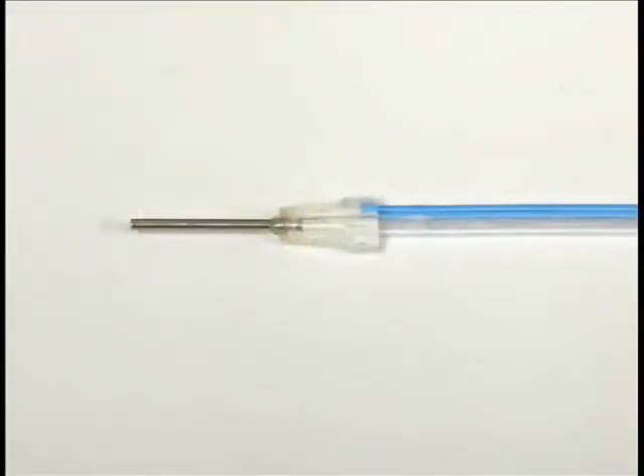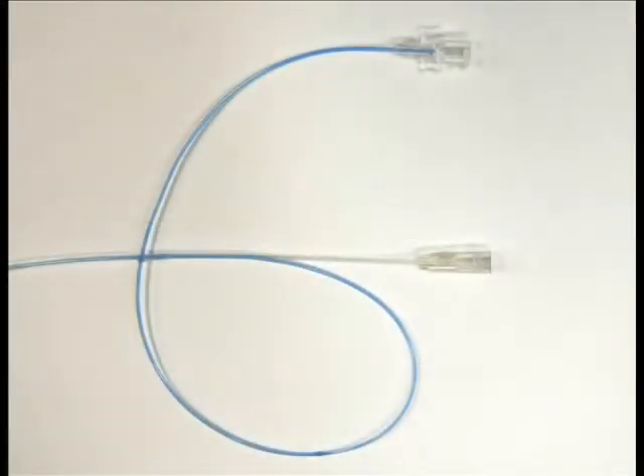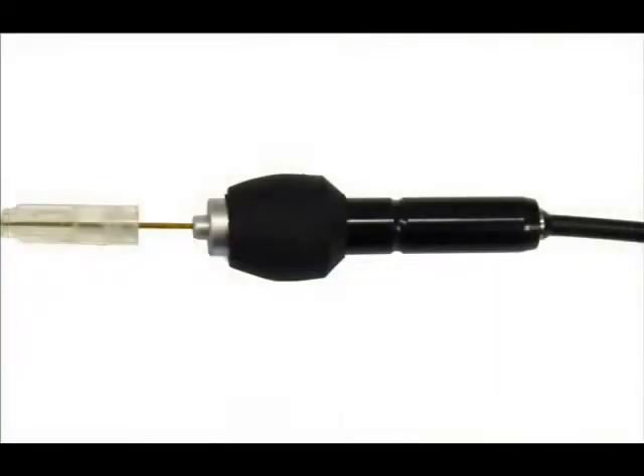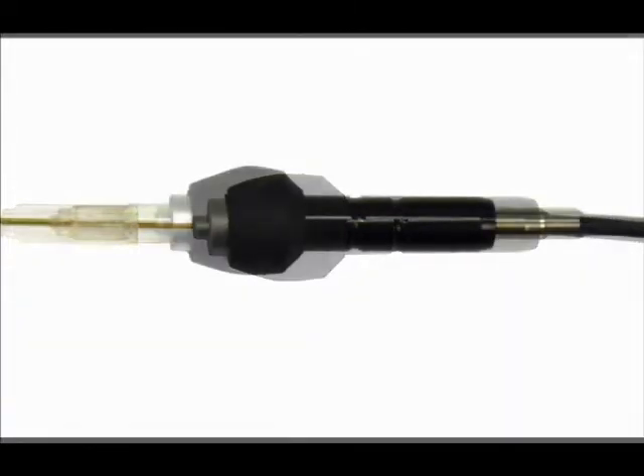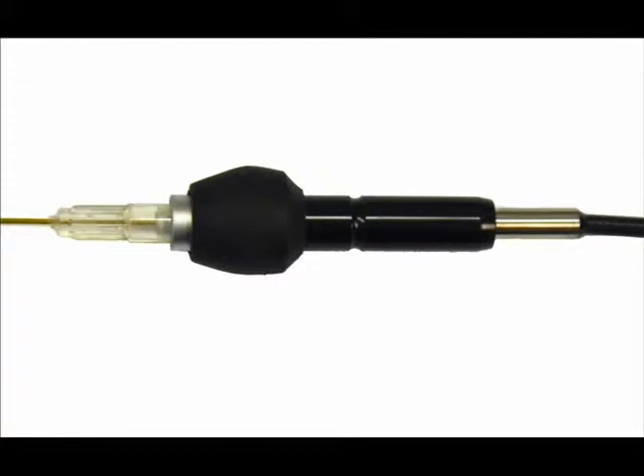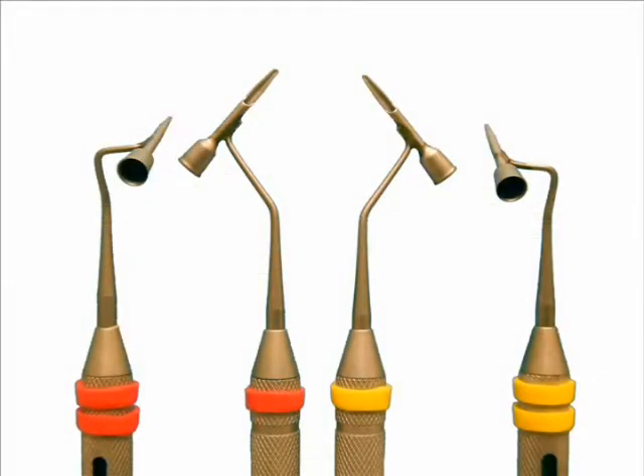The periodontal endoscopy sheath eliminates the need to sterilize the fiber, which significantly extends the life of the fiber, and is designed to deliver water irrigation to keep the endoscope lens clear. The spring action locking mechanism on the fiber creates a tight, secure adaptation of sheath window and fiber lens for clear in-focus images. The periodontal endoscopy explorers are sterilizable dental instruments that hold the sheath fiber complex, allowing for intraoral use.